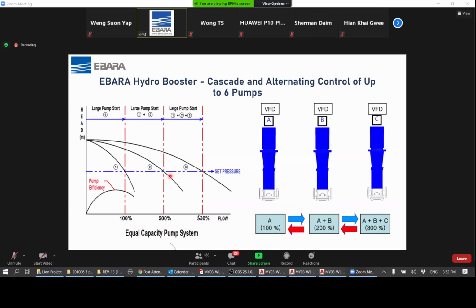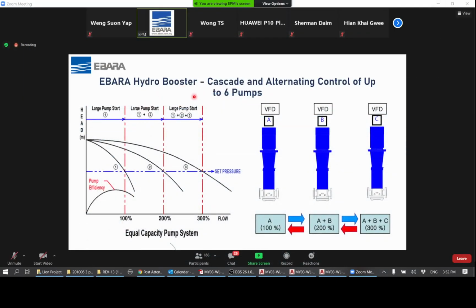At the same time, there is also alternating control, meaning that if the first pump has run and stops, the next pump to run will be pump number 2. When pump number 2 has run and stopped, the next pump to run is pump 3. In such a way, it shares equal running hours. All this is done by the controller of the variable speed drive. The intelligence of such a system comes a lot from the brain of the system, which is the controller. So Ebara hydro boosters allow for both cascade and alternating control of up to 6 pumps in one system.